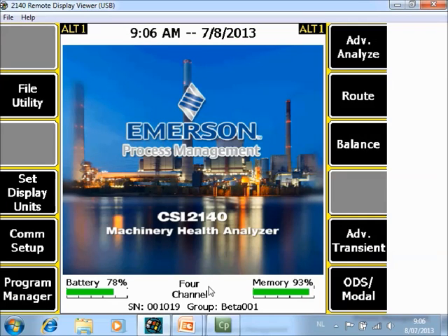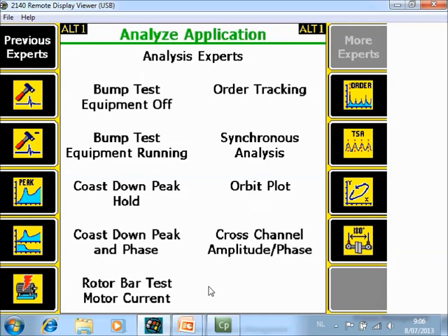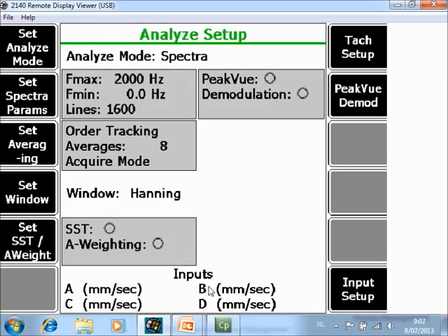On the home screen of the CSI Machinery Health Analyzer, go to Advanced Analyze. Then press F7 for more experts and F8 for order tracking. You can start it directly by pushing F3, but first let's quickly review the setup in F1 Manual Analyze. As you can see, I am also measuring from 0 to 2000 Hz, 1600 lines, 8 averages — but now with the order tracking process.